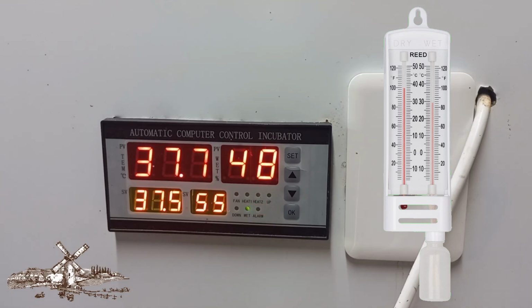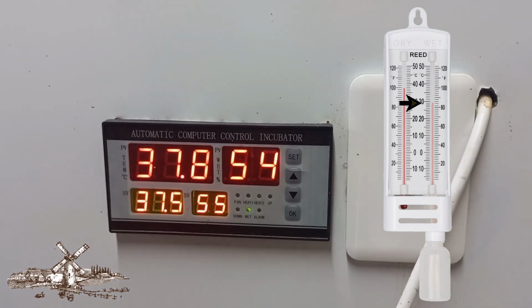and you will expect to see that humidity measurement go back up to 55. Now, as the humidity increases, you'll also see the wet bulb thermometer temperature also increases. And you'll see that the temperature on my wet bulb has gone from 27 degrees Celsius up to 29. So by doing that, that means that my wet and dry bulb is telling me that the humidity has been climbing over the last 30 minutes.